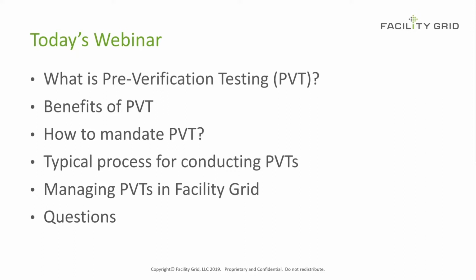What are the typical procedures for conducting the PVTs? So PVTs shall be conducted following completion of all startup and pre-functional activities for the associated equipment. As a minimum, it is recommended to complete PVTs for one equipment instance per each major equipment type. For example, if on your project you have several air handling units, VAV boxes, pumps, chillers, and so forth, what you would want to do is conduct one PVT for each major equipment type, like an air handling unit, or maybe a chiller, a pump.